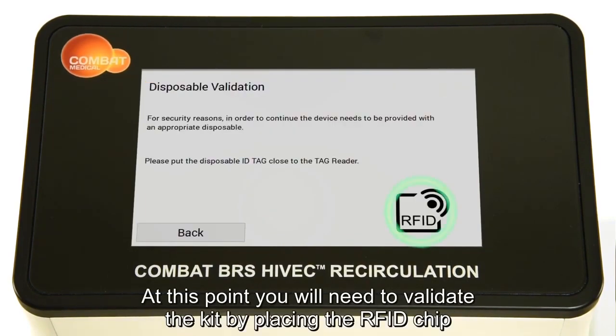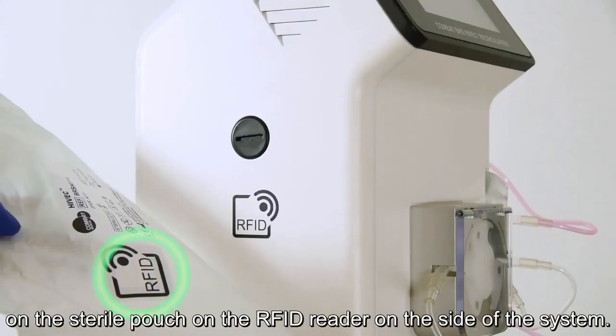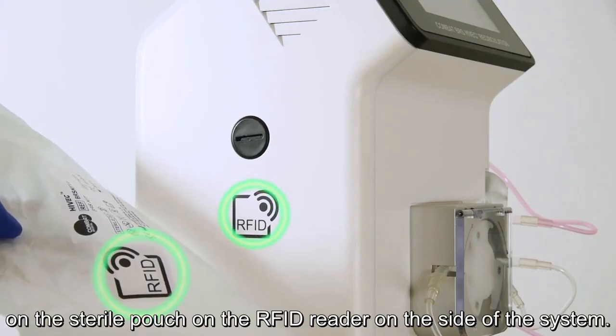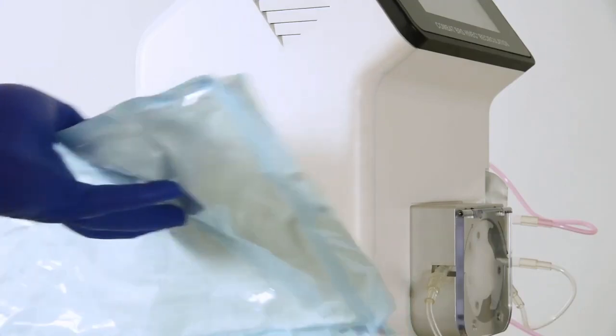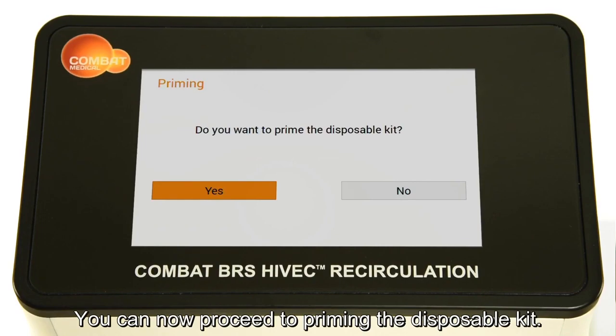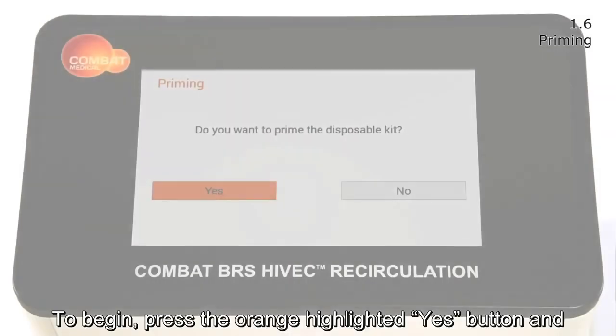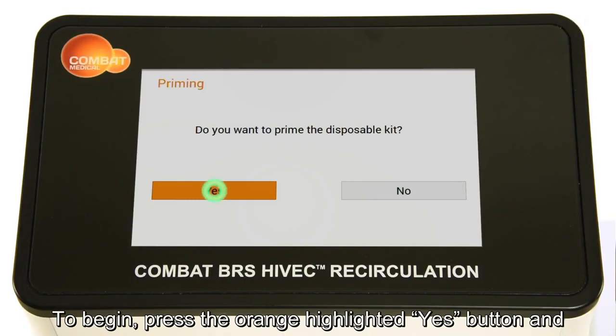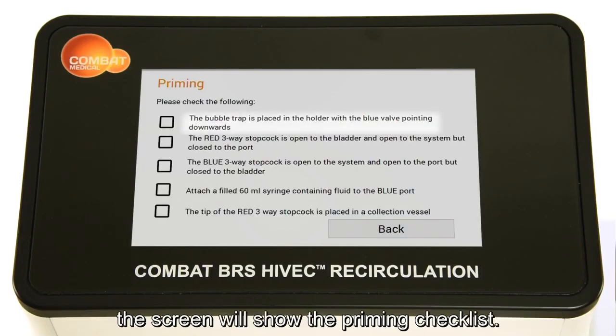At this point, you will need to validate the kit by placing the RFID chip on the sterile pouch on the RFID reader on the side of the system. You can now proceed to priming the disposable kit. To begin, press the orange highlighted Yes button and the screen will show the priming checklist.